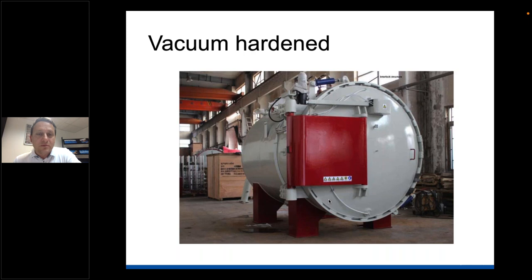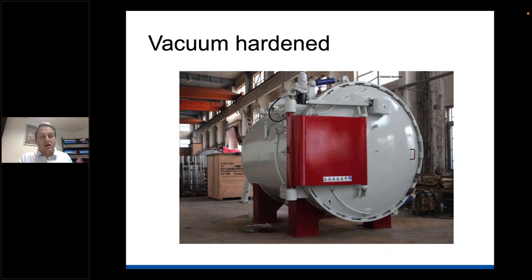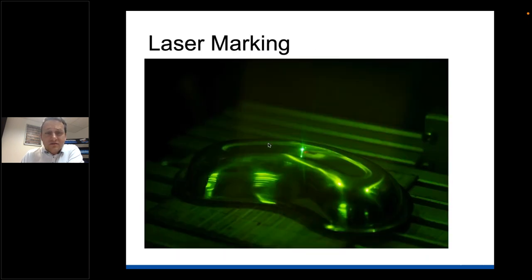Vacuum hardening is another important process. Once we have our forging with the particular carbon content - a higher carbon level means the device will come out harder - something like a rongeur would be made from higher carbon steel than an artery forcep. Unless you're a very large company, this is generally sent out to a professional vacuum hardening company. That's what a vacuum hardening machine looks like. Laser marking is one of the final processes.